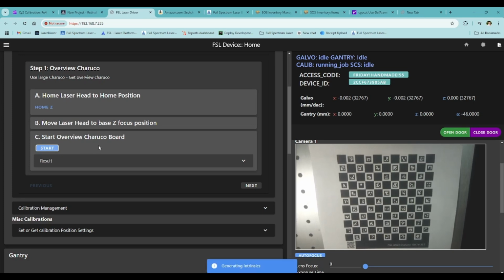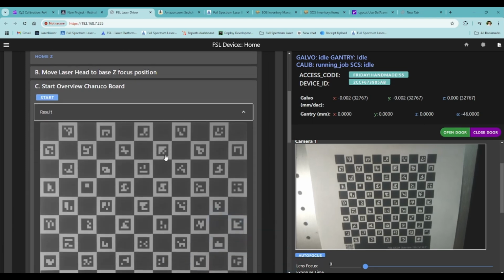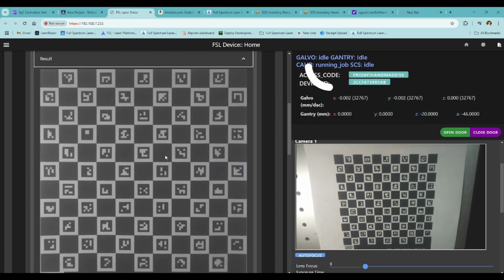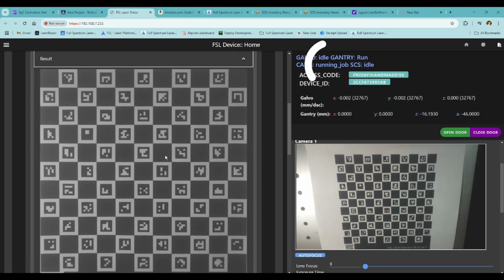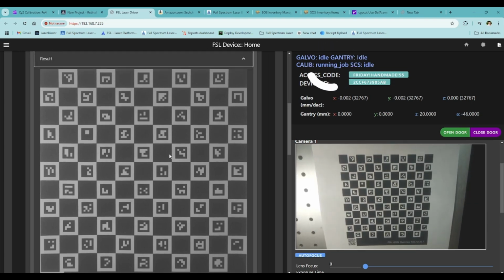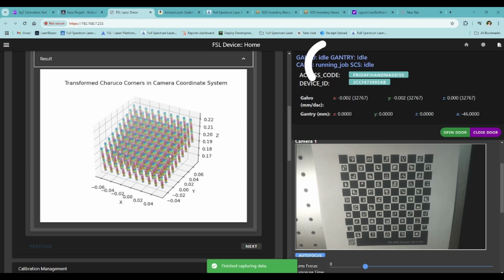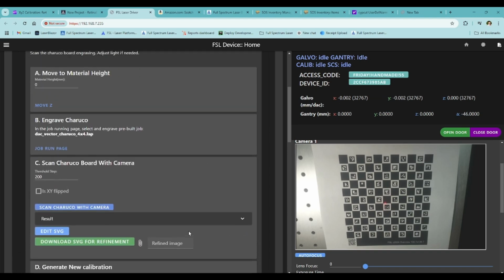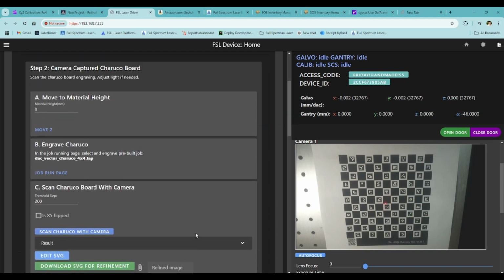The machine is now generating the intrinsics for the camera capture. We can monitor the calibration stage in the top right corner. Now that the status has switched back to idle, we know this step is complete. Next, we need to ensure that all dots are visible and there are no blank spots. If you notice blank spots, there may be excessive light shining on the Charuco board, which should be reduced or removed. Alternatively, the Charuco board itself may be damaged. Select Next, as we are now ready for step 2.